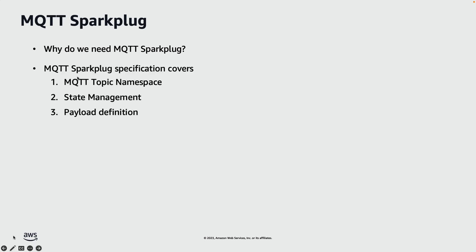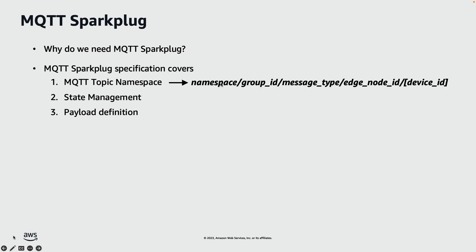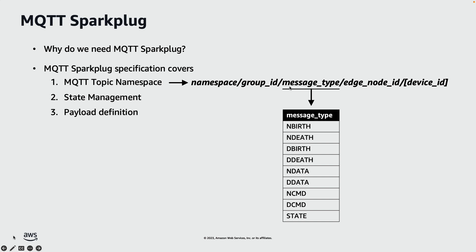The Sparkplug specification tackles this challenge for industrial IoT by providing a standard way of defining topics, state management, and payloads. Now let's look at each of these three areas, starting with the topic namespace. The spec provides semantics to standardize how topics are created. Here is a structure that shows various segments that make up a typical topic. The namespace indicates payload encoding, the group ID represents a group of devices, and the message type represents different types of messages, including whether it's a data or a command message.